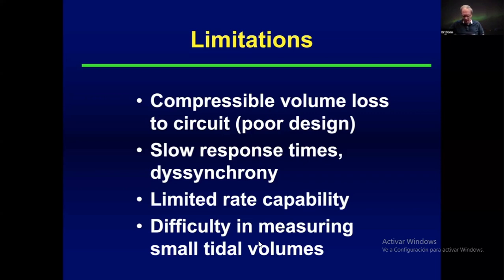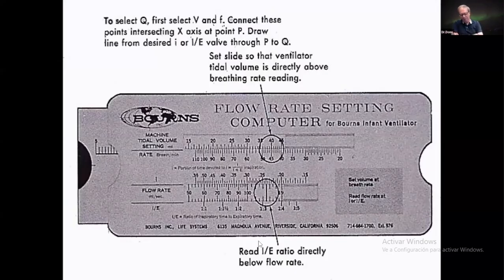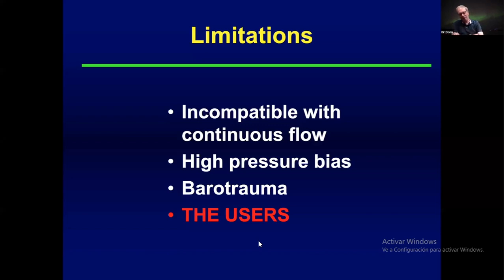The Bourns company, I think, was cognizant of this. And they provided us with a bedside computer. See, it says computer. And this is how we estimated the amount of volume that we were giving the baby. What it did was it would help you to calculate compressible volume loss in the circuit, and then subtracting that from what you thought you were giving the baby gave you a very crude estimate of the amount of tidal volume that the baby was actually receiving. It was incompatible with continuous flow, so that in between breaths, the baby wasn't getting any help from the bias flow circuit. There was a bias among many healthcare providers that although this was a volume targeted or volume limited device, it created very high pressures and therefore resulted in barotrauma.